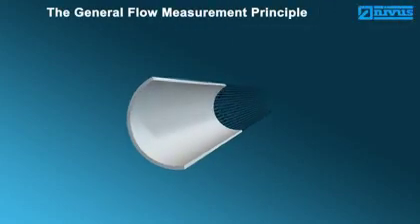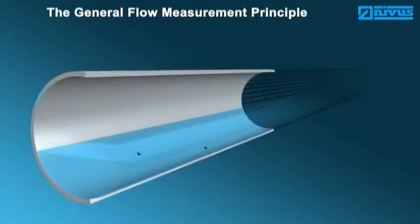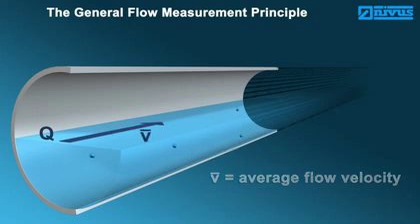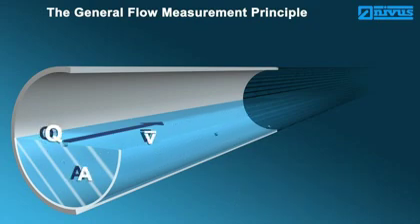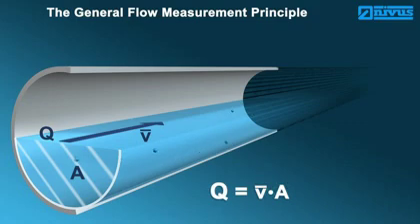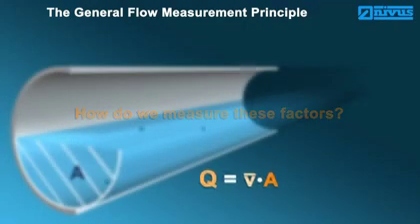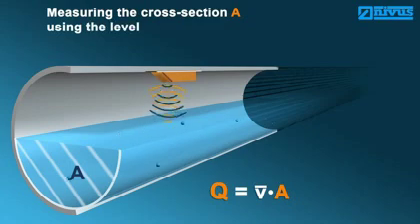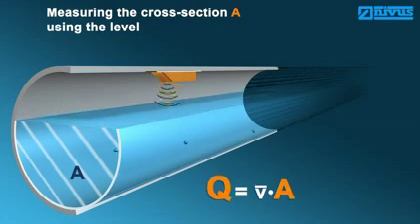The flow measurement principle. Flow cannot be measured directly. There are various factors required to detect the flow Q, such as the average flow velocity and the flow cross-section. From this the general formula is obtained: Q equals V average times A. The flow cross-section A is determined by continuously measuring the level in consideration of the channel shape. If the level changes, the flow cross-section will change accordingly and hence flow will change as well.